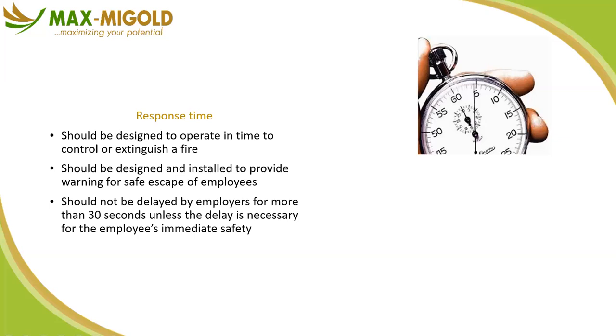But one basic trick is to have multiple muster points. When I say evacuate, it is the time the last person gets to the muster point, not the time the first person gets to the muster point. Because the guy on the ground floor who is making a phone call, or is at his desk, hears the alarm, leaves everything he was doing, and is at the muster point right away, in less than 30 seconds, fantastic.